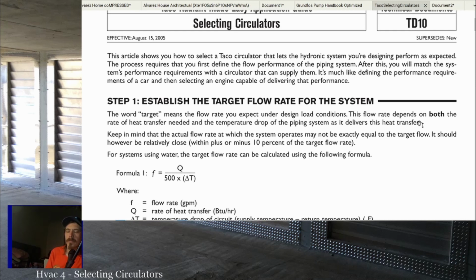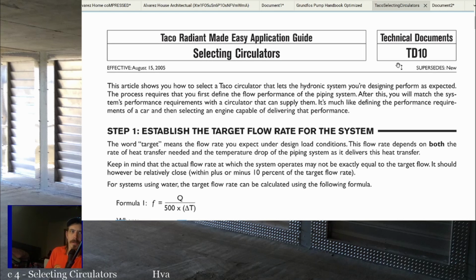And you'll find as we go through this stuff throughout the year, doing circulator sizing now, and then when we do gas pipe sizing, and when we do duct sizing, and anything else, we're talking about the pressure loss through the piping. We always end up talking about pressure loss somewhere, and it's not much different with a pump. It's the amount of friction we have to overcome, the amount of static pressure you have to overcome with the fan, with the gas piping, how much pressure you have to overcome in the length of your gas pipe. All those things. It's all about, what are we working against? So, Taco's article on selecting circulators is the best one I've ever found. And again, this will go up on Google Classroom, but it walks you through everything.